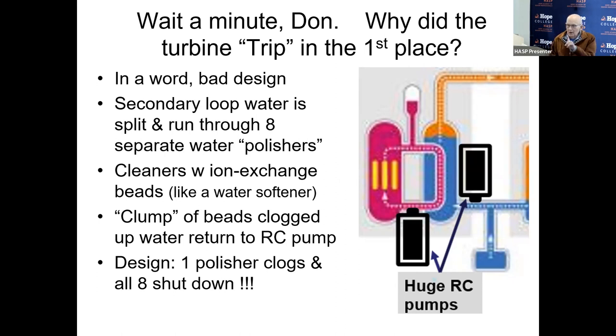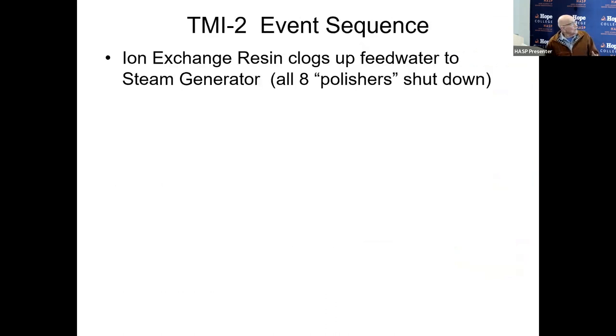One polisher, there are eight polishers. The condensate water is going to go back and become heated, boiled again. And it's a large volume of hot water, but it all should be cleaned. It should be run through a polisher. There are eight of them. They're pretty big, but there are eight of them. The design is such that if one clogs, all eight shut down. Why in the devil would you design it that way?